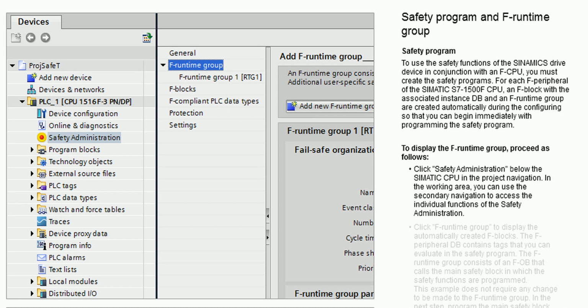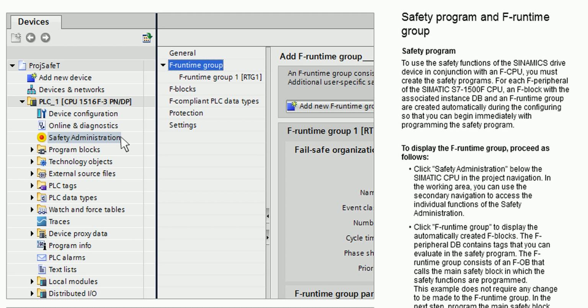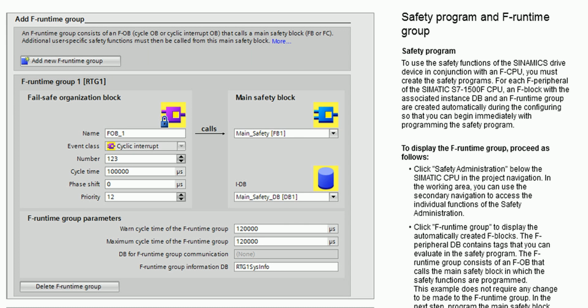In the working area, you can use the secondary navigation to access the individual functions of the safety administration. Click F runtime group to display the automatically created F blocks. The F peripheral DB contains tags that you can evaluate in the safety program. The F runtime group consists of an FOB that calls the main safety block in which the safety functions are programmed. This example does not require any change to be made to the F runtime group. In the next step, program the main safety block.